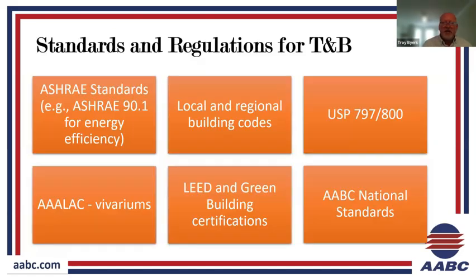Okay. Some of the standards and regulations that come into play and are referenced in testing and balancing are ASHRAE standards. So the design under ASHRAE standard 90.1 for energy efficiency. And again, these go into consideration for new design, but sometimes existing buildings were designed prior to the advancements in these energy standards and energy codes that exist today. And so that's where we look at our local regional building codes and see how they may be retro-commissioned in an existing building. USP 797 and 800 applies to pharmacies. And so pharmacies are now getting upgraded to comply with new standards, like the new standard USP 800 for air changes and pressurization. So TAB is a very critical element there.